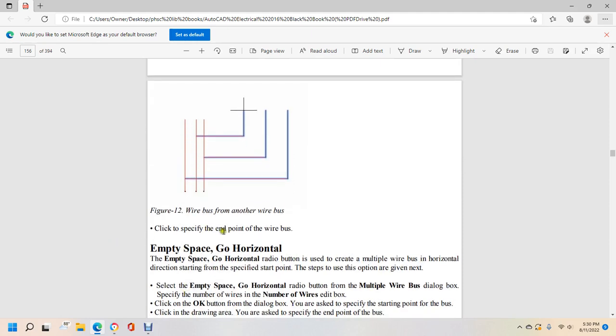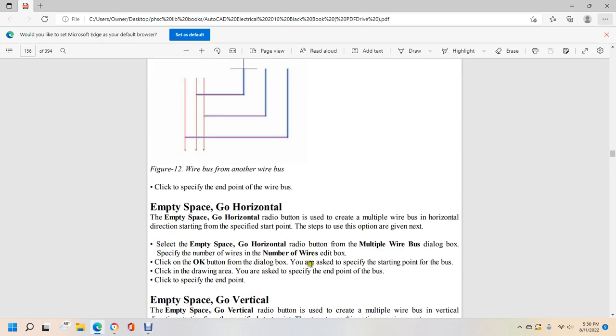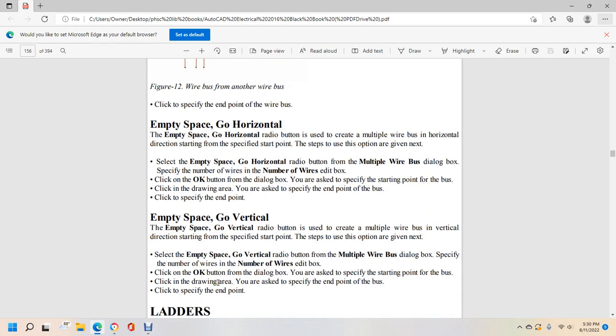Click to specify the endpoint of the wire bus. Using the 'Empty space go horizontal' or 'Empty space go vertical' radio buttons, you can create a multiple wire bus in the horizontal or vertical direction from a specified start point. Specify the number of wires in the edit box, click OK, specify the starting point in the drawing area, then click to specify the endpoint of the bus.